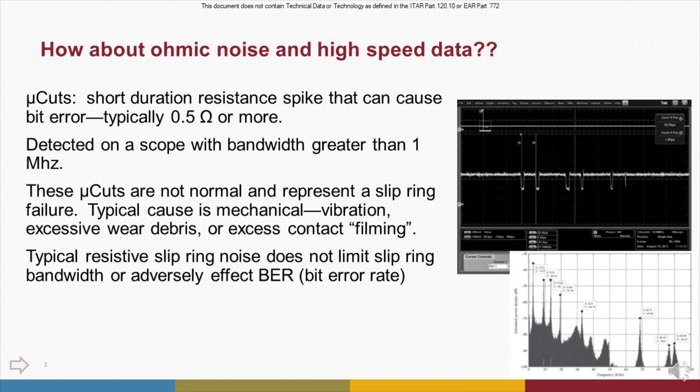There is another type of resistive noise that has come to the forefront when passing high-speed digital signals through slip rings. This noise is in the form of very short duration resistance spikes that can cause bit errors, and such a noise event is frequently called a microcut. These are detected on oscilloscopes at measurement bandwidths of greater than 1 megahertz and can become problematic if they reach values of several hundred milliohms. It is important to understand that these microcuts are not normal and represent a bit of slip ring failure if they cause reduction in bit error rates below acceptable levels.